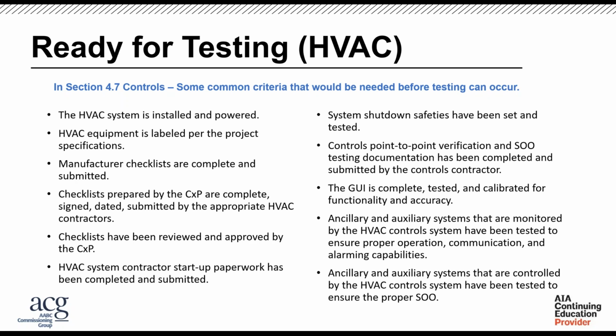So prior to testing, you want to make sure that that coordination has happened, and make sure that even though you might only control the actual BAS system, you're able to run through all of the different sequences as designed. And if you need to have the manufacturer's control people there, you need to bring that there as well. So those are some of the things that I try to look at when we say ready for testing. And it's never perfect. Every situation is different. However, it's one of those things that we try to keep a big eye on and try to coordinate as best as we can.